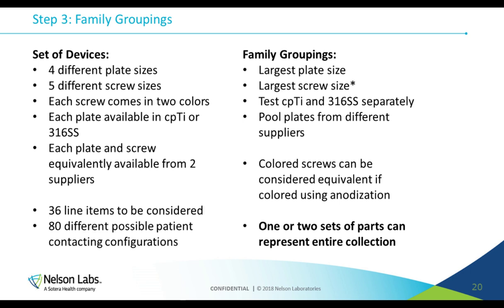And the way that we did it is we start to make family groupings, looking at one thing at a time. So of the plate sizes, the worst case plate, or one that would be representative of all the plates, would be the largest plate. So that has the greatest opportunity to release chemicals from its surface. If it's dirty, there's more surface area there that can allow that. So the largest plate size is definitely the worst case.